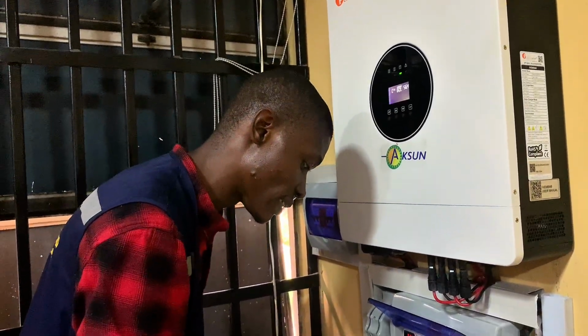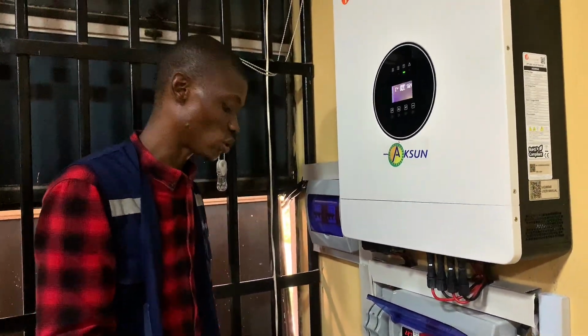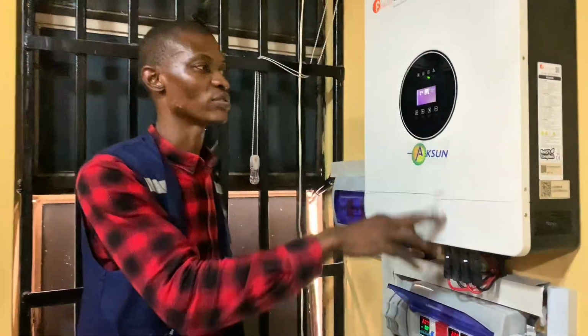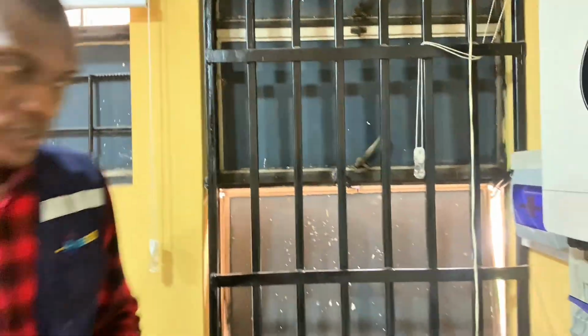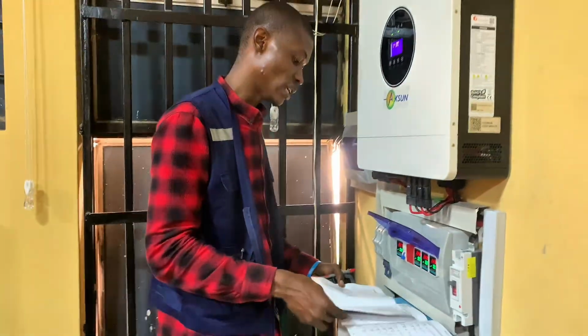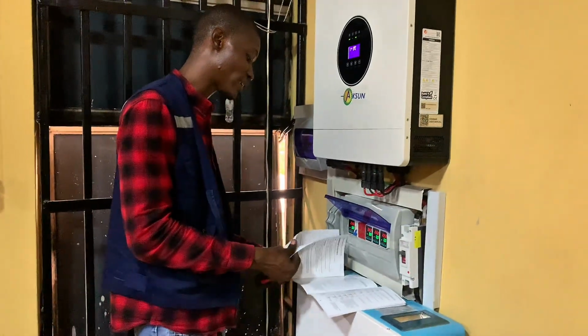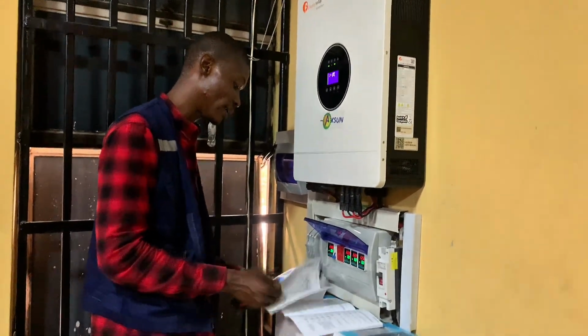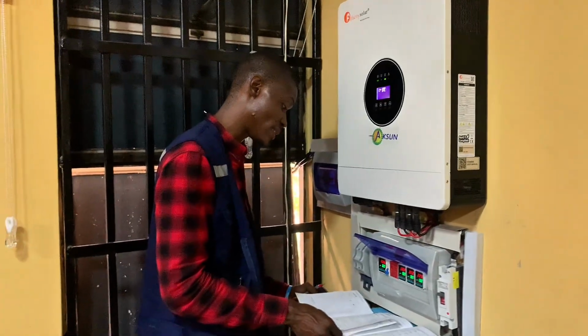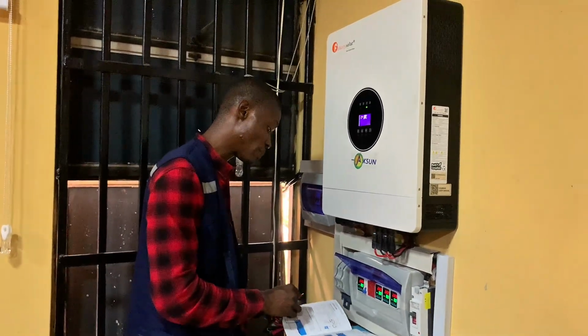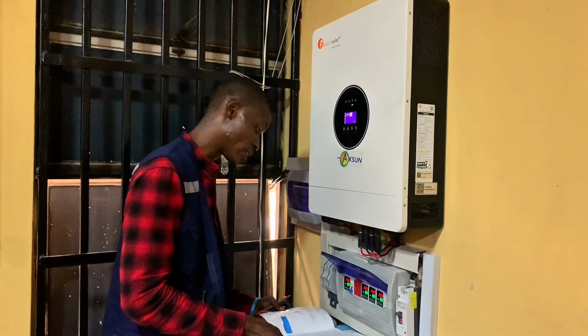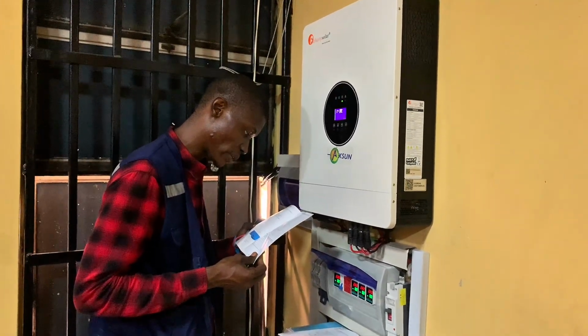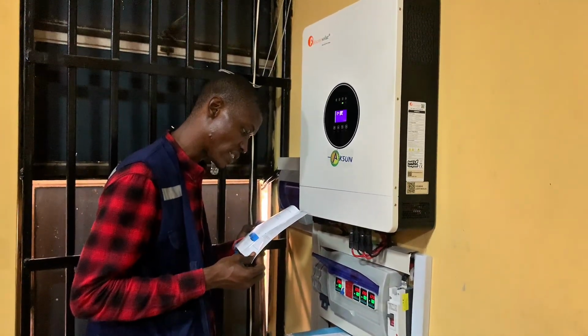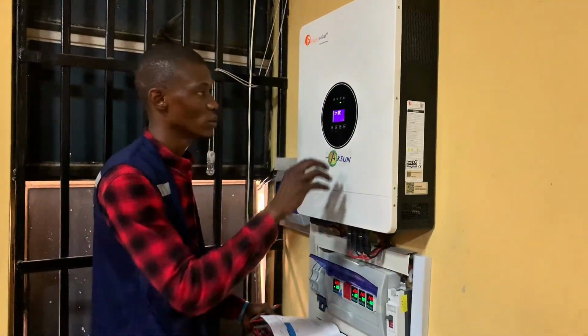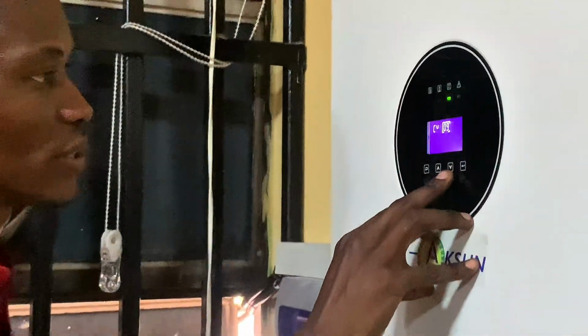Setting 9, that's bulk charging voltage. What I do here is check the type of battery you are using and check its bulk voltage. Whichever type of battery you are using, the bulk voltage will be specified in the manual or on the tag on the battery. So based on my manual here, our bulk charging is 58.4. Let's do that.